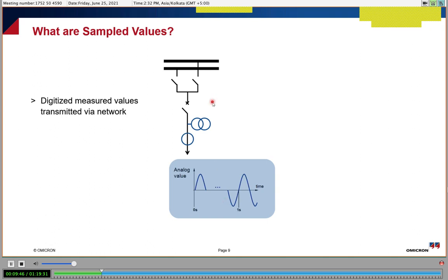As per this drawing or picture, we have these busbars, isolators, circuit breaker, and then we have these instrument transformers and a feeder. So to receive this current and voltage data, currently, in most substations, more than 95% of substations right now, we use copper cabling between the field CT/VT to the kiosk of the relay and other kinds of meters, other instruments.